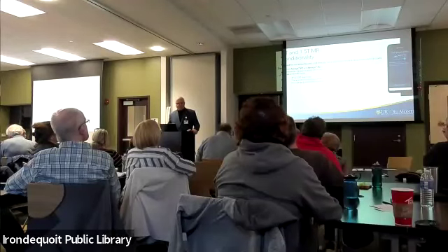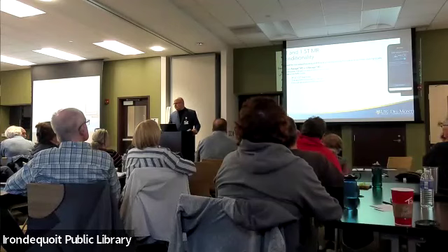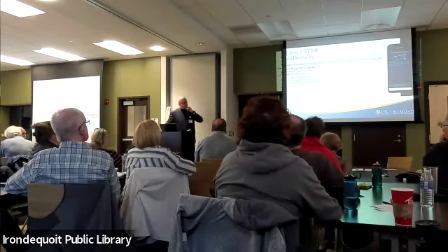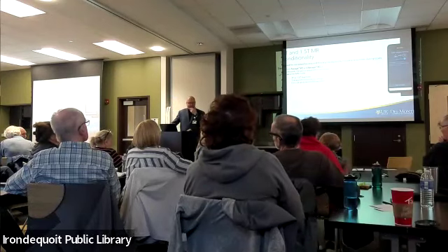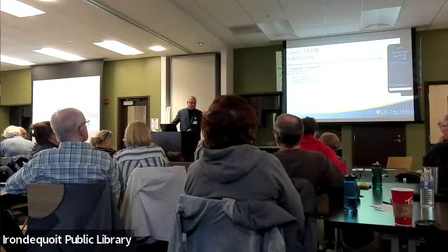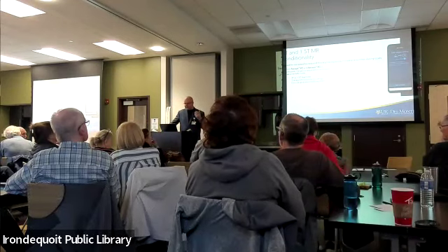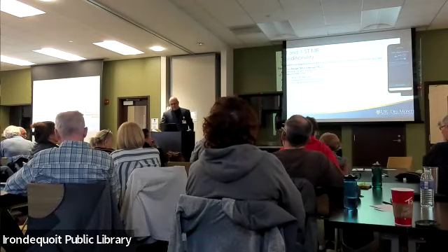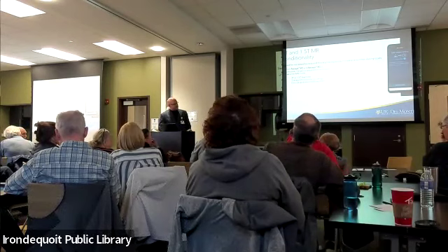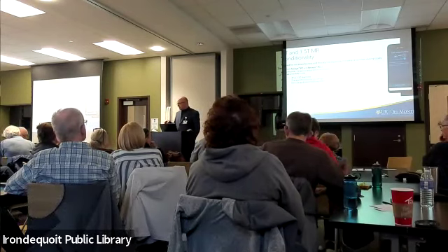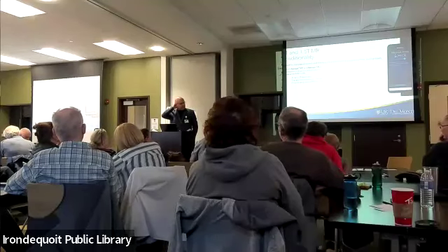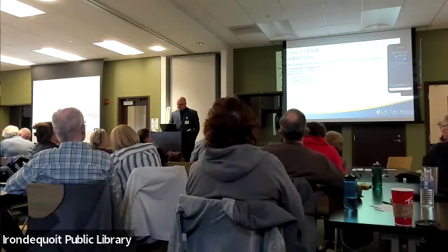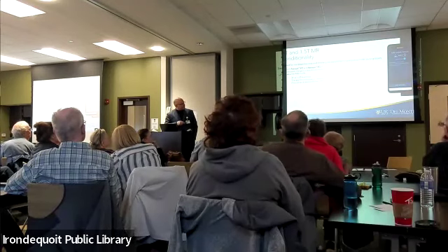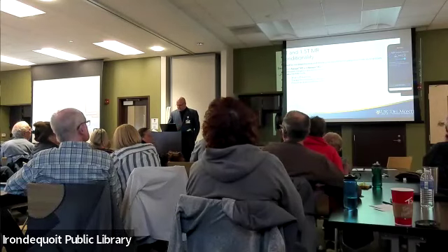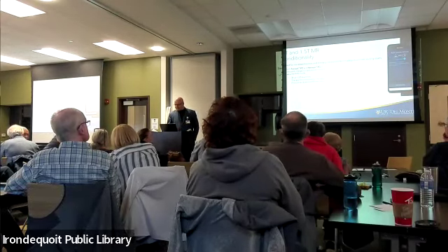So we implant, the majority of our devices we implant are the Medtronic devices, which have been available since back in 1987. They are MRI compatible, both in 3 Tesla, which refers to the power of the machine, the magnetic strength, and 1.5 Tesla. It's currently the only one that allows DBS therapy to continue to be on when you're actually having your MRI done, so it can hopefully help your MRI be done more comfortably. You'll see on the right-hand side of the screen, your patient controller, you can actually put your device into MRI mode yourself if needed, if you're in a place that's not close by to us.